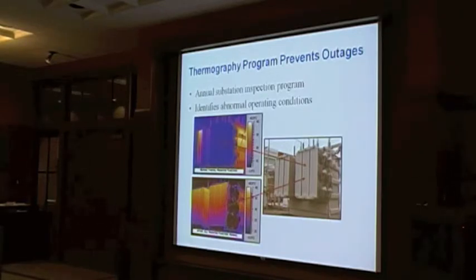It would shut down, and UT would be off, we would be off of Kauai. But if the other safety devices did not work, we were facing a catastrophic failure here. But you can see, once the corrections were made, the oil is coming in at the top, it's being cooled by the fans, and it's being redistributed back through the transformer. So this is a good find for a program that's, I guess, a $35,000 a year type program. We get around the system and look at all these components.